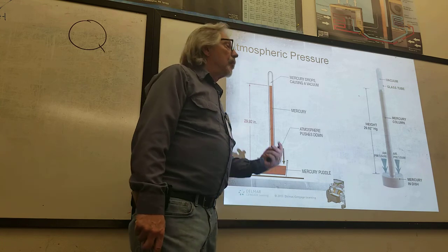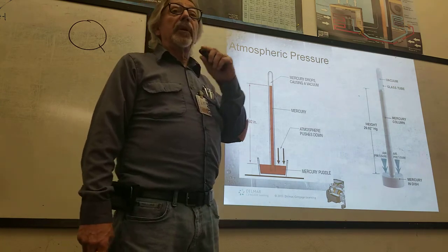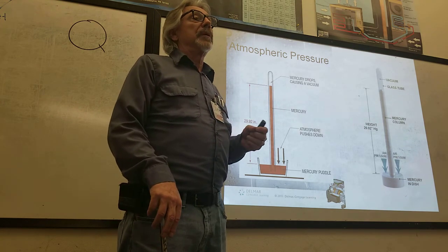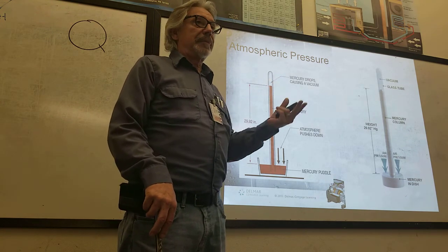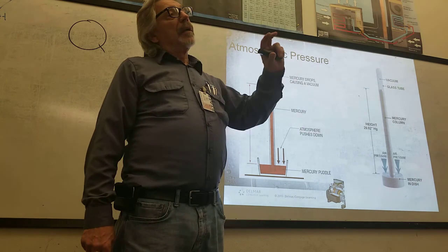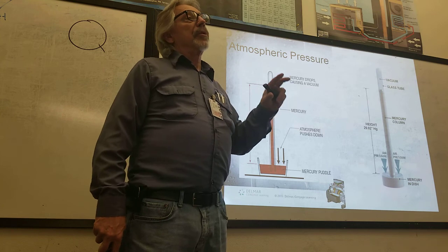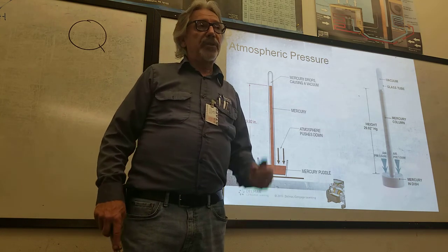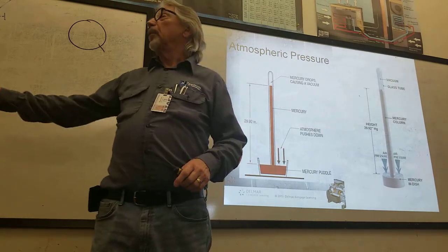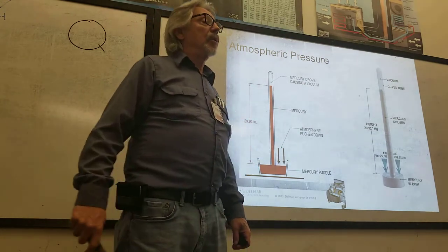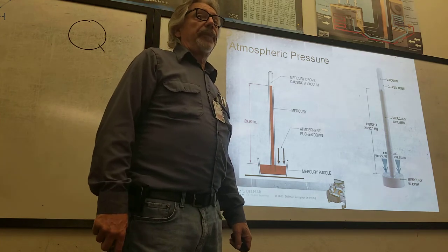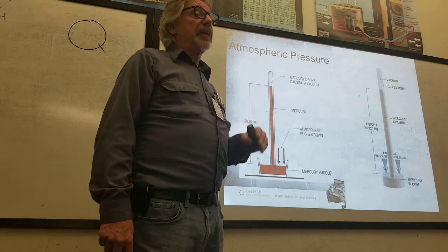So when you watch the weatherman, that's what I did every morning. I watched what kind of ambient temperature I'm gonna be working in, not because I wanted to feel comfortable, it's because the temperature greatly affects the pressures in our refrigeration system and our conditioning system. So what we're going to read on the gauges is going to depend on what the outdoor temperature is. Okay, so that makes a difference.